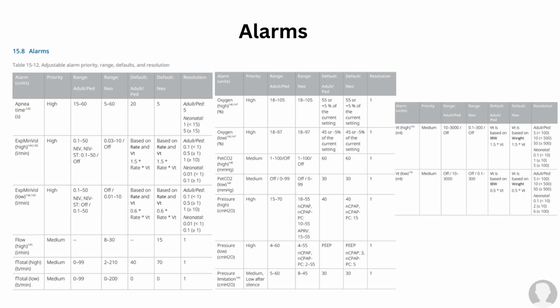Here are a list of alarms for the Hamilton C1. This chart includes adjustable alarm priority, range for adult peds and neo, defaults for adult peds and neo, and resolution. Alarms can be set for parameters including pressure, volume, flow, oxygen concentration, and respiratory rate. Users can adjust alarm limits based on patient needs and clinical conditions.